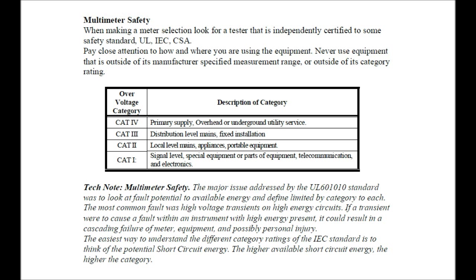CAT IV: primary supply overhead or underground utility service. CAT 3: distribution level mains fixed installation. CAT 2: local level mains appliances and portable equipment. CAT 1: signal level special equipment or parts of equipment — telecommunications and electronics.